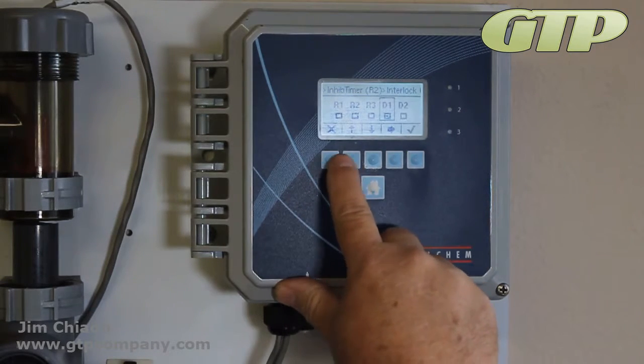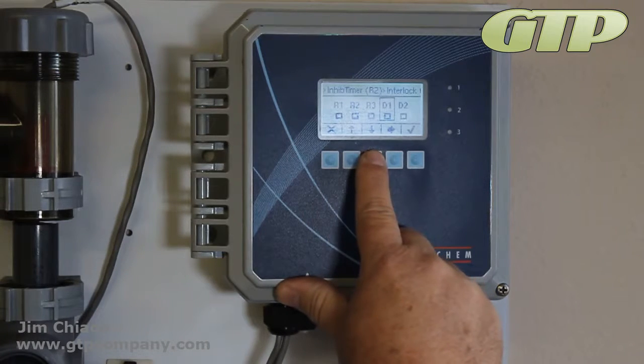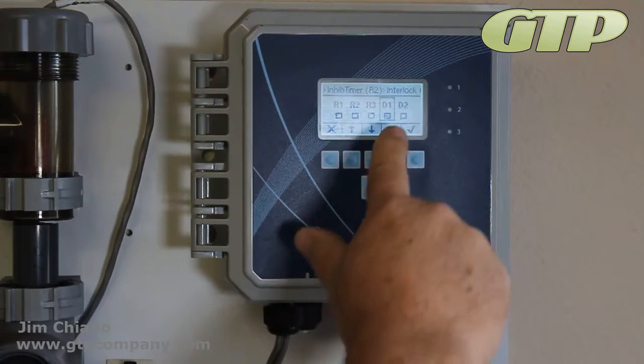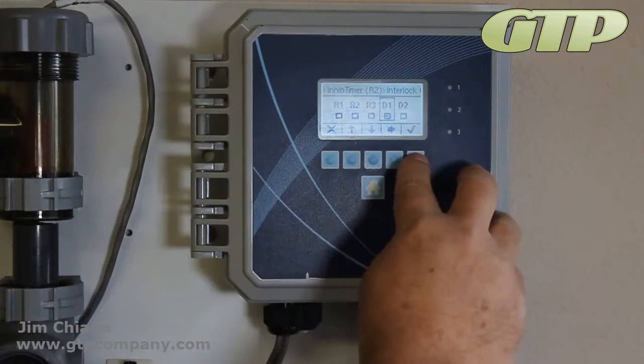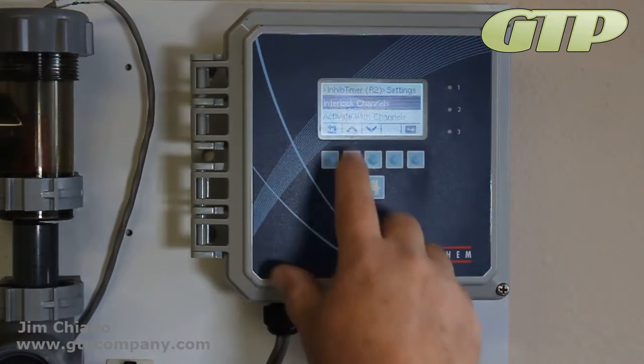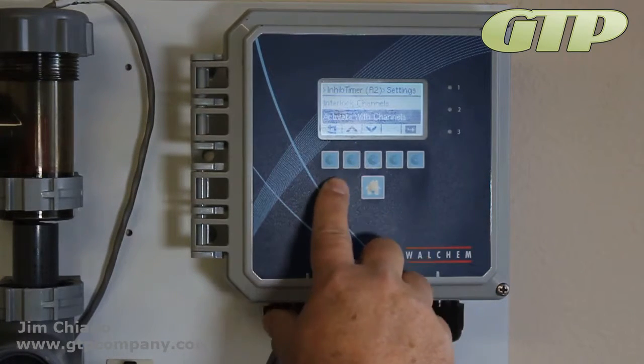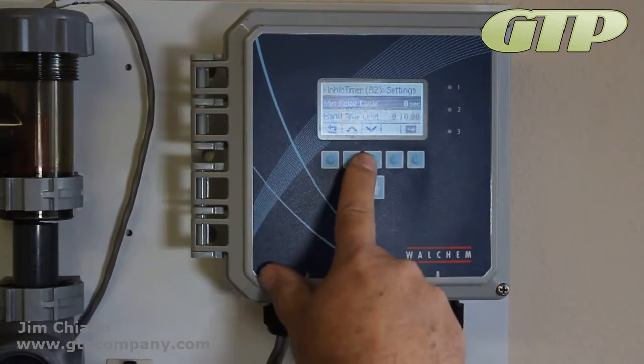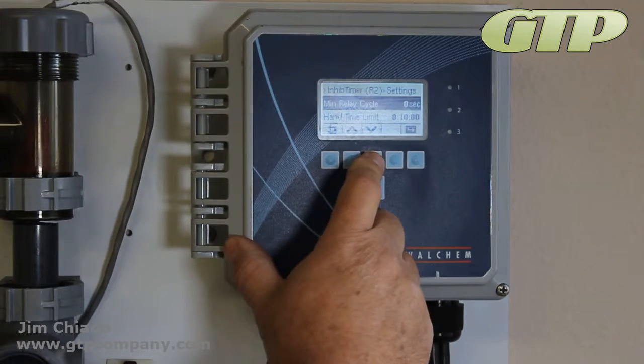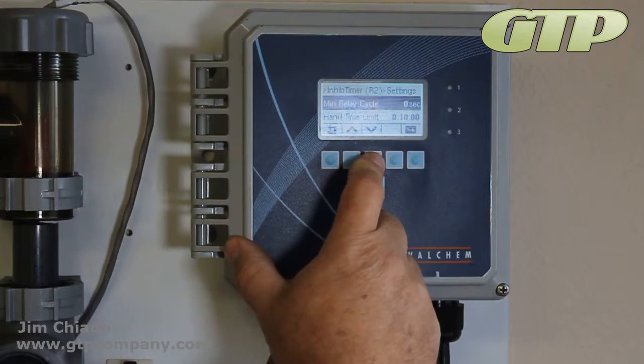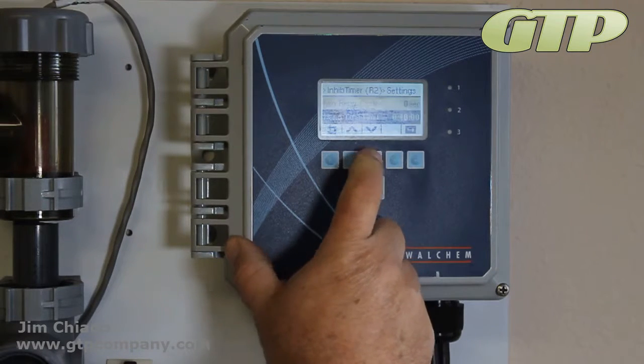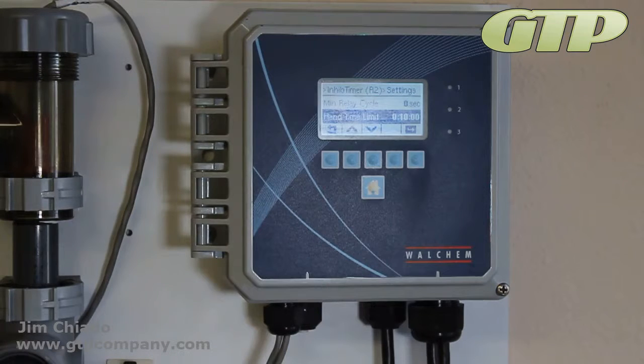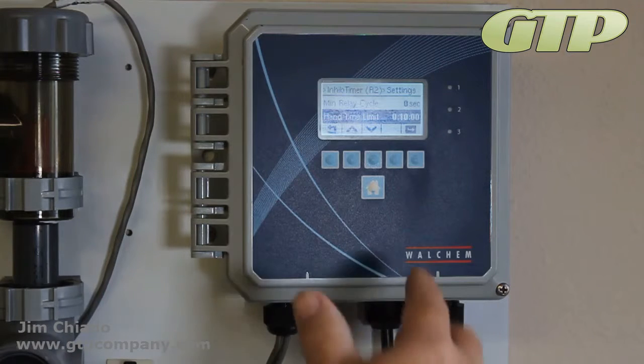So we can pan over, we can use the up arrow key to make sure it's on, or the down arrow to make sure it's off. D1 is the flow switch, so if the flow switch is off, we don't feed anything. Activate with channels doesn't make sense on this one. Minimum relay cycle doesn't make any sense on this one either, because it comes on for 10 minutes or 15 minutes, whatever we set it at. Hand limit time: the hand limit timer is when we put it to the hand position, how long will it stay on before it switches back over to auto.